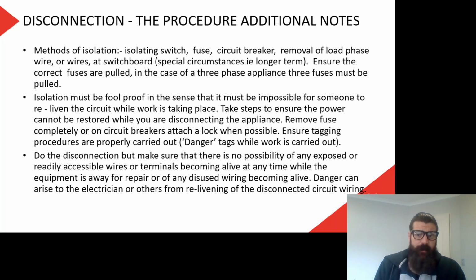Isolation must be foolproof in the sense that it must be impossible for someone to reliven the circuit while work is taking place. Take steps to ensure the power cannot be restored while you are disconnecting the appliance. Remove the fuse completely, or on circuit breakers attach a lock where possible. Ensure tagging procedures are properly carried out, so danger tags and so forth. Yeah, so we've discussed at length locking circuit breakers. In the case of fuses, there's a couple of ways that we could do that. My preferred method would be to remove the fuse from the fuse holder and put those fuses in my pocket. So I've got them on me. Nobody else can come and reconnect those fuses or plug them back in because I've got them with me.